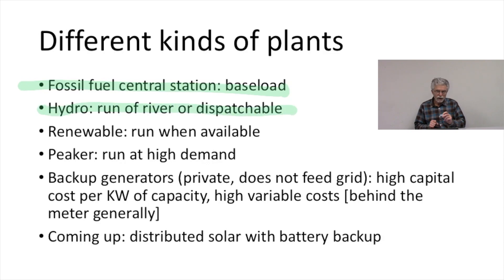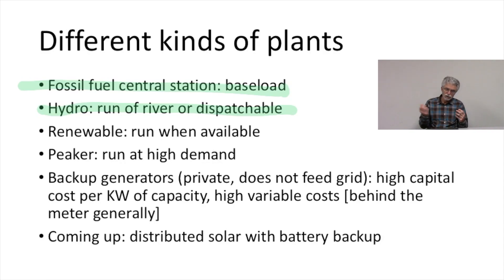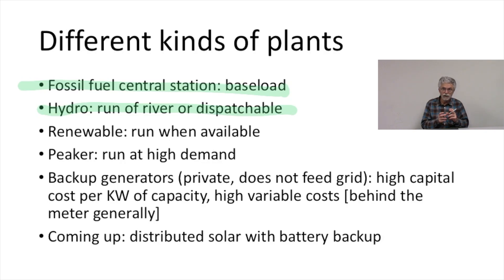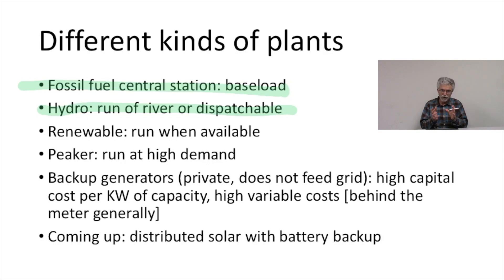Then there's hydro, which comes in a couple of flavors. A hydro facility can be a run-of-river plant, where you constantly generate according to the flow of water past the facility and storage is less important, or you can think about a hydro plant as a dispatchable storage unit. The water behind the dam is a huge store of potential energy you can use later as needed, so a hydro facility can be either a constant-generate source as water runs through, or a dispatchable source of power.